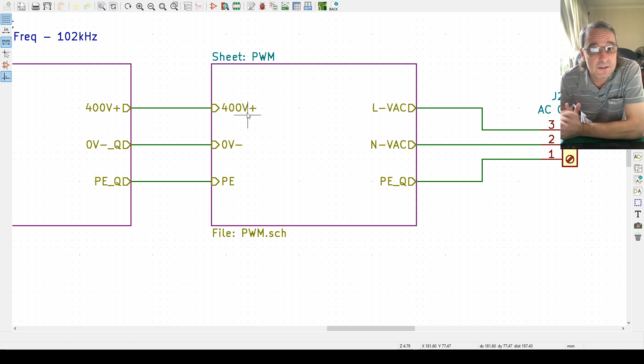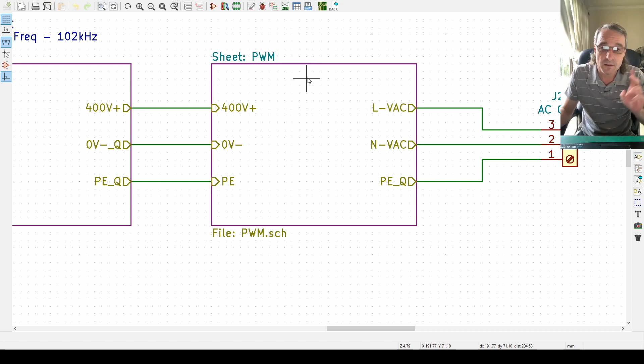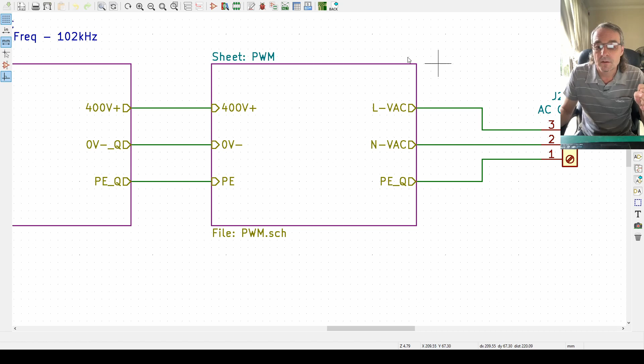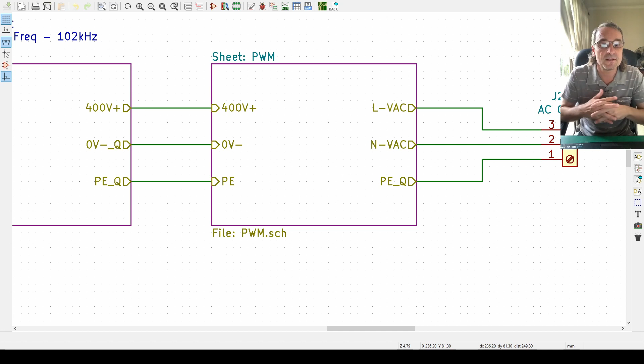We're using pulse width modulation because we don't know what the load is going to be. It's not always going to be a full 2 kilowatt, because not all your motors are running all the time, depending on what the diversity of the board is. You might have a duty and a standby pump in the same board, so your utilization factor or your diversity of the board might be 50%, so we might only actually be using 1 kilowatt of the 2 kilowatt. But to make it efficient, we use pulse width modulation. So we invert it back to AC and regulated AC, and we'll get our live and neutral out again, plus the primary earth, and we'll take that to the AC out.